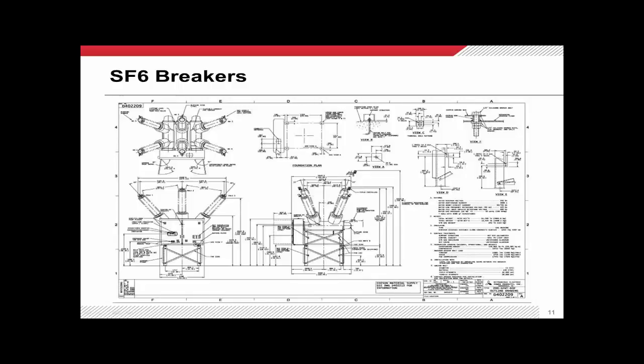Please pull out the first drawing, which is an outline drawing of a circuit breaker. Up in the top left there's a plan view of the circuit breaker, and you'll notice the bushings are numbered. That numbering carries through to the wire designations for all leads coming off your current transformers. If you don't follow this correctly, you won't wire the current transformers to the proper relay scheme and won't be able to achieve overlapping zones of protection.